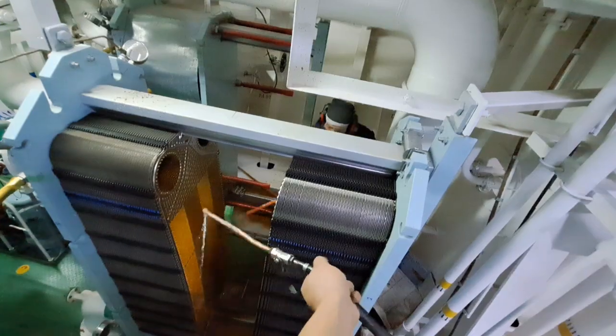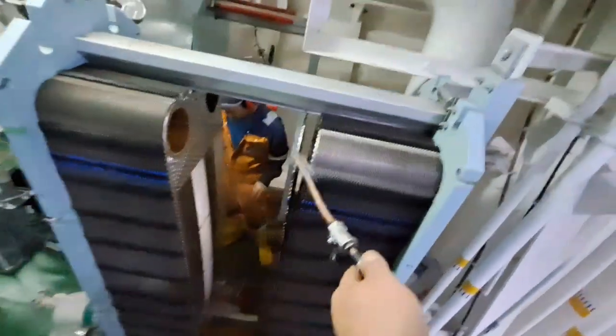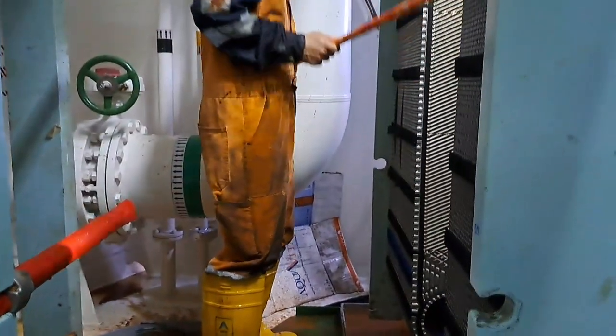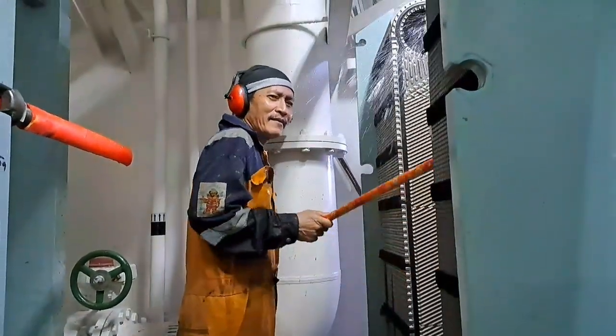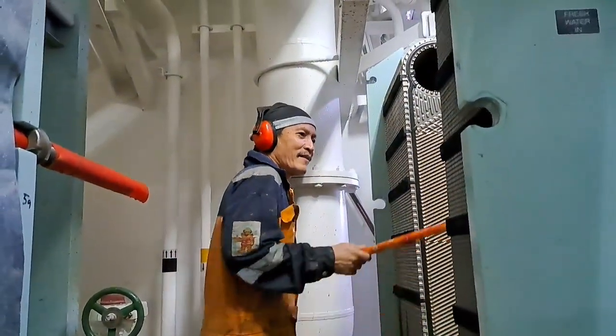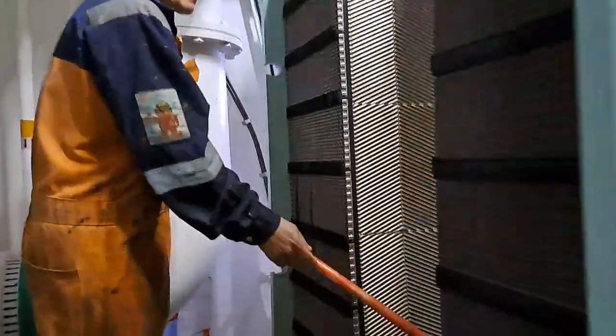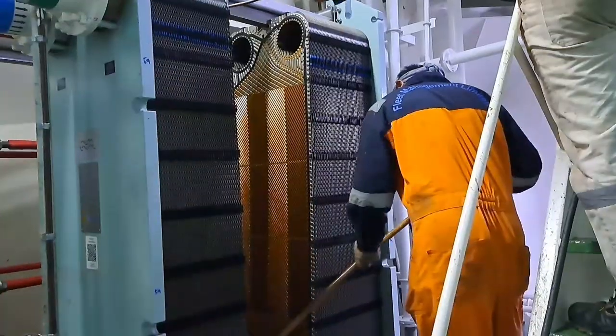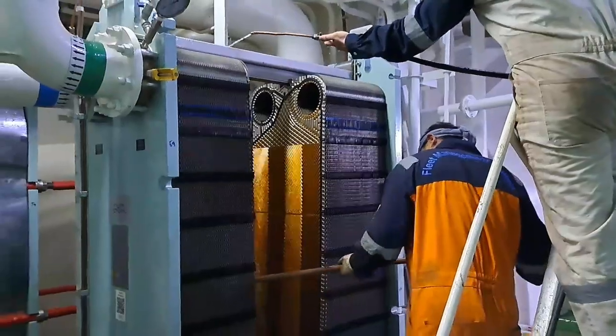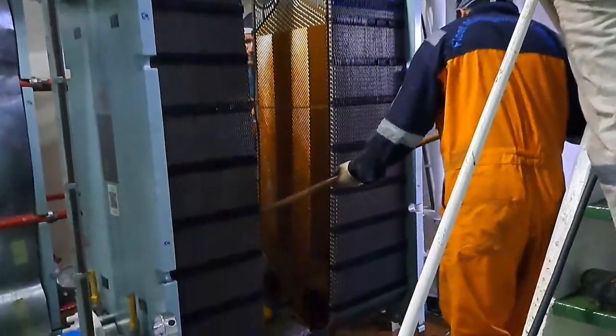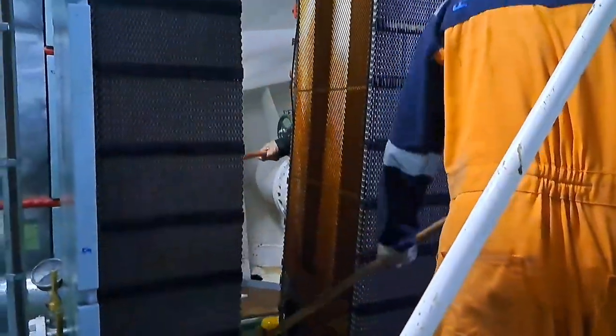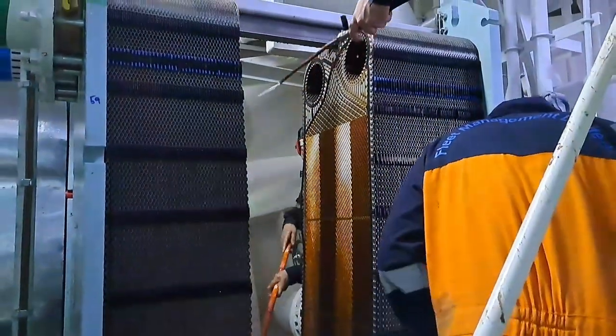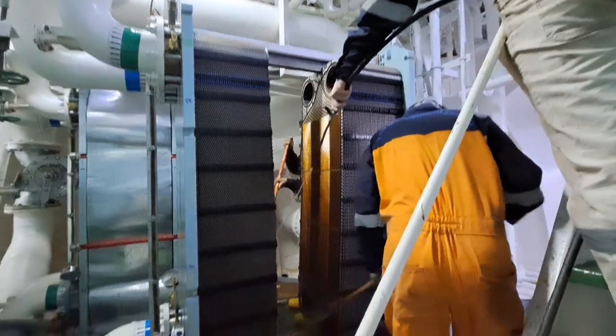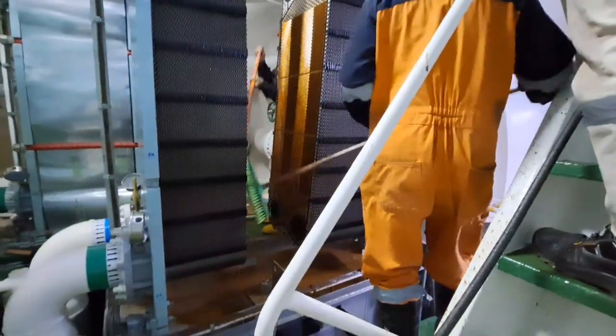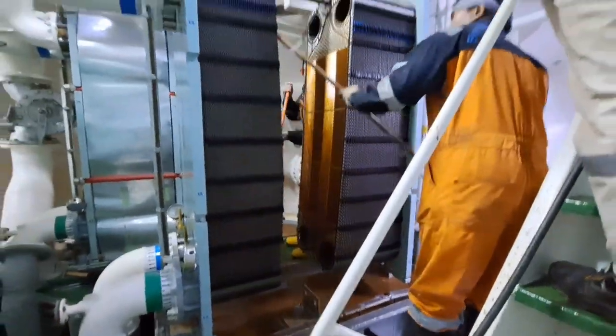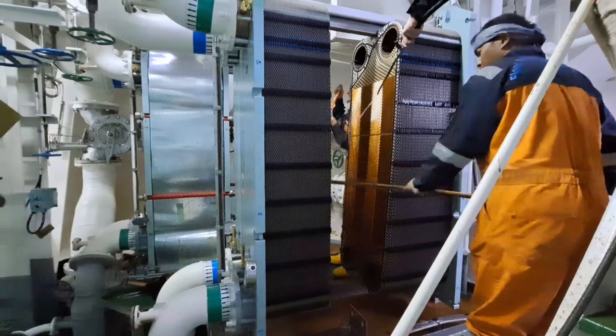Gasket failure is the easiest thing to spot. If the gasket fails, the pressure will drive fluid through to the leak, and you'll see the fluid dripping from your plate heat exchanger. You'll be able to easily detect the failure since the fluid will seep from the faulty gasket. Disassemble your plate heat exchanger and remove the plate with the failing gasket as well as the plate adjacent to it. Then, if you have new parts on hand, just replace them.